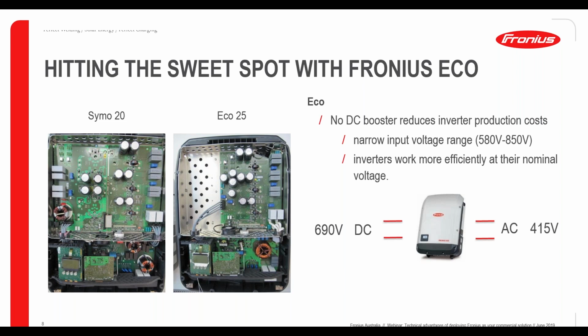Is there anything you wanted to add there, Dimi? One thing that is known in industry as well: it's much easier to convert from higher to lower voltage. There are really two reasons for it. The electronics don't work as much. The other one is that the voltage drop will typically be less. So in terms of commercial sizing and commercial deployment, it's always the rule of thumb that it's better to have higher operational voltages from the inverter point of view.